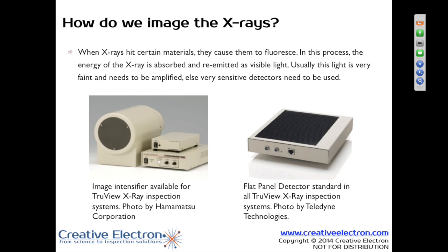Best case scenario, an image intensifier is going to give you 256 shades of gray, which is not a big deal if you're doing visual inspection. But when you start doing inspection with a computer program or computer processing, you really want more than 256 shades of gray — and that's where digital flat panel detectors have come into place. In that detector is essentially another scintillator screen, with photodiodes underneath taking the light and converting it to a digital electronic signal, sending that signal to a computer. Image intensifiers use CCD cameras or even digital cameras to pick up that image, so they're picking up a 256 grayscale image. You may have a digital camera on the back that gives you a 1024 by 1024 output, but you're still only getting 256 shades of gray.